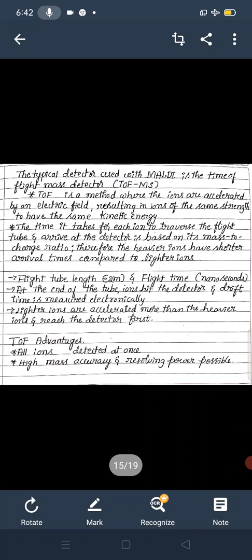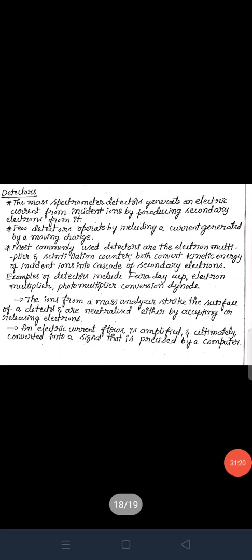Let us know about the detectors. At the end of the flight tube, ions hit the detector. The mass spectrometer detectors generate an electrical current from incident ions by producing secondary electrons from them. A few detectors operate by inducing a current generated by a moving charge. The most commonly used detectors are the electron multiplier and scintillation counter. Both convert kinetic energy of incident ions into a cascade of secondary electrons. Examples of detectors include Faraday cup, electron multiplier, photomultiplier, and conversion dynode. The ions from a mass analyzer strike the surface of a detector and are neutralized either by accepting or releasing electrons. An electric current flows, is amplified, and is ultimately converted into a signal that is processed by a computer.